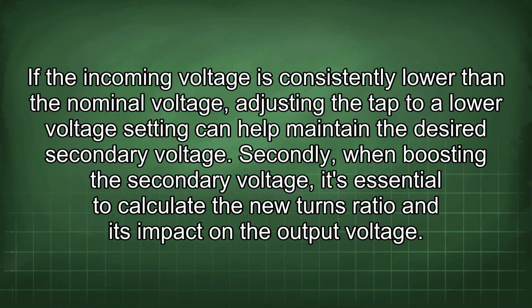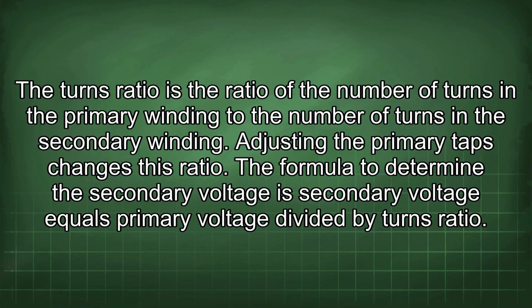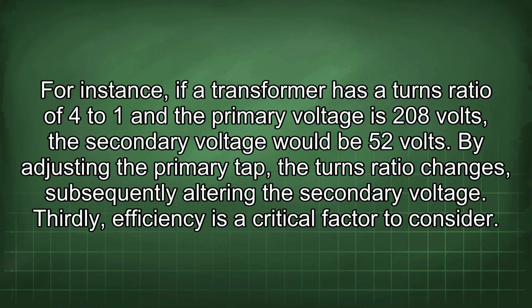Secondly, when boosting the secondary voltage, it's essential to calculate the new turns ratio and its impact on the output voltage. The turns ratio is the ratio of the number of turns in the primary winding to the number of turns in the secondary winding. Adjusting the primary taps changes this ratio. The formula to determine the secondary voltage is secondary voltage equals primary voltage divided by turns ratio. For instance, if a transformer has a turns ratio of 4:1 and the primary voltage is 208 volts, the secondary voltage would be 52 volts. By adjusting the primary tap, the turns ratio changes, subsequently altering the secondary voltage.